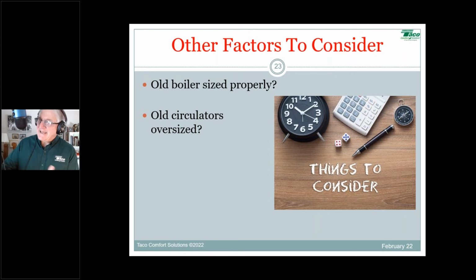And there's really no way of taking that into account, because if you oversize your circulators, you're getting more flow than you need all year long. As it gets warmer out, you're getting less and less efficient because you're short cycling that boiler like crazy. You can even short cycle your boiler with oversized circulators in the colder conditions. That's going to change this equation, and there's really no way to factor that in other than inferring. Even if you put in a new system and oversize the circulators, you're changing the equation with no way to quantify that. That's why we talk about delta T circulators, because they minimize that short cycling and minimize the impact of oversized circulators.